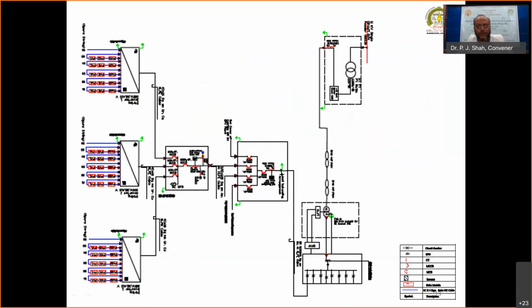Now this is the single line diagram for the 300 kVA power plant, which we are going to install. This is our transformer from the 11 kV line. The CTPT unit is in the custody of MSEDCL, and it is connected with some DO fuses and an OLTC. We have an OLTC transformer, on load tap changing, to maintain the voltage. This is the changeover switch, connected to the DG set. Once the grid fails to supply, our power plant also goes mute; it will not deliver any power because it is grid connected. So with the help of this changeover switch, power is delivered to the load only by the DG set, and the PV plant is disconnected.